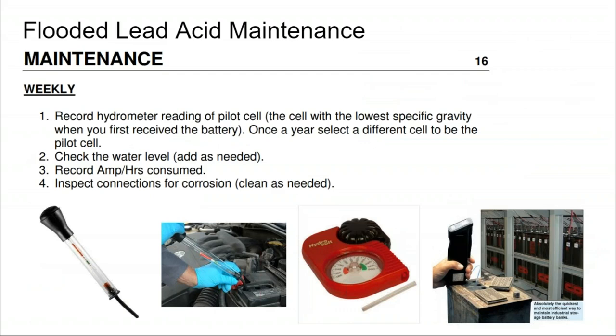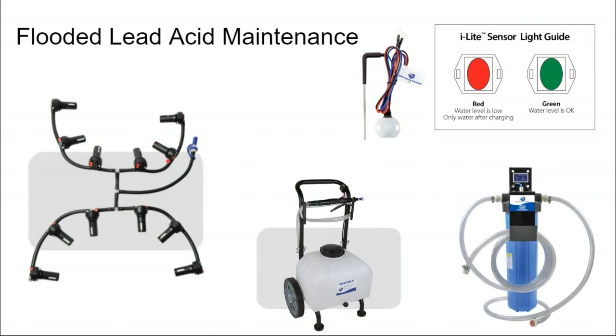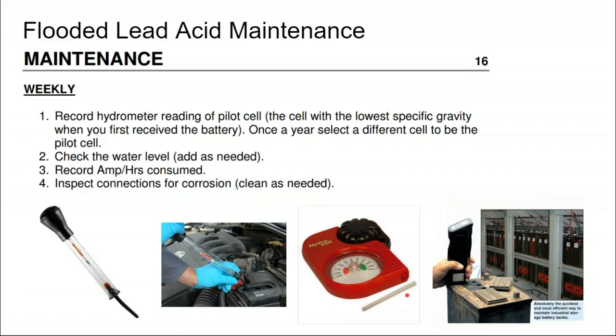Another suggested task, much more useful for battery health diagnostics, if not weekly, is preferably a monthly task: take the cap out of the battery and stick a hydrometer down into it. It takes a little bit of liquid out of the battery, which in general isn't something you want to do, but it measures the specific gravity of the liquid, which is the only way to adequately judge a battery's health.